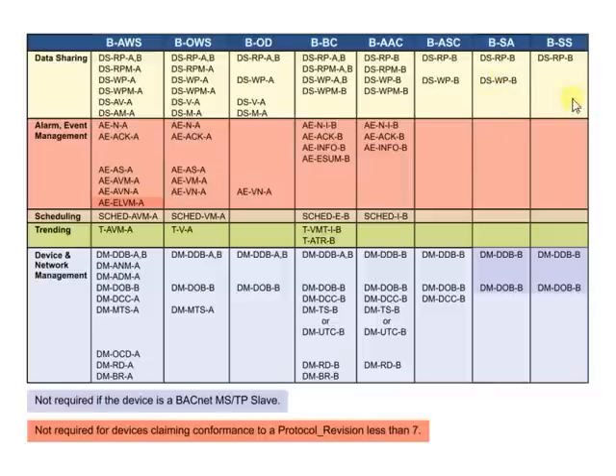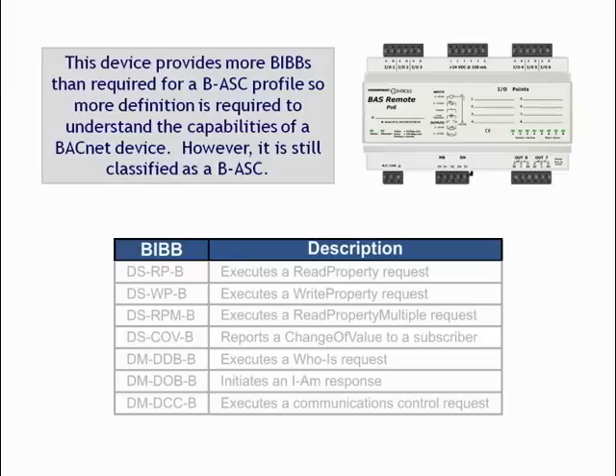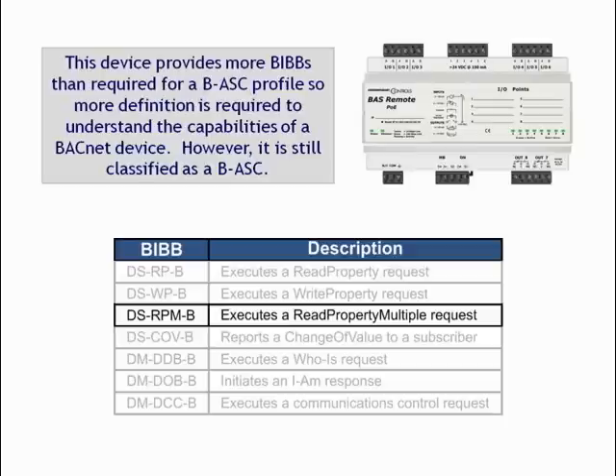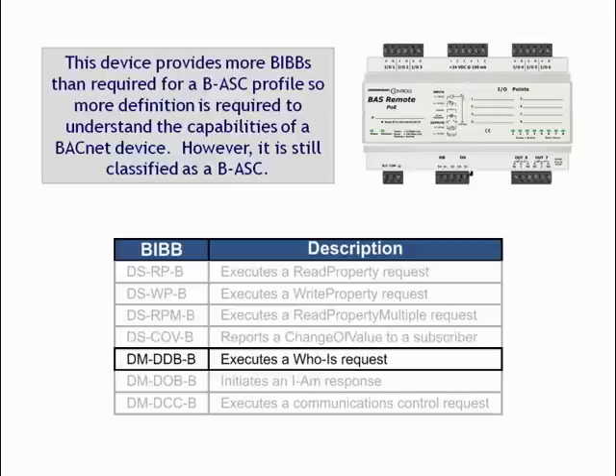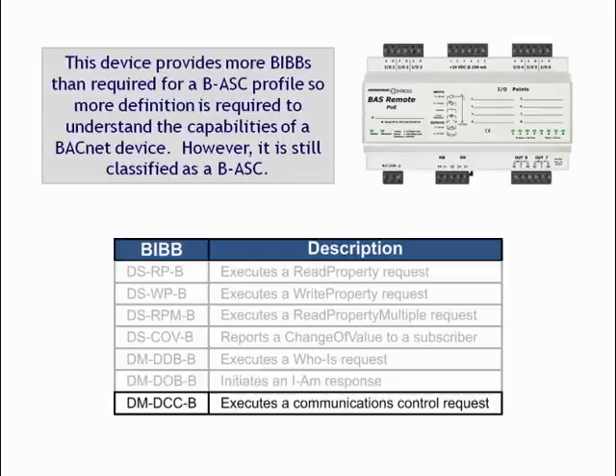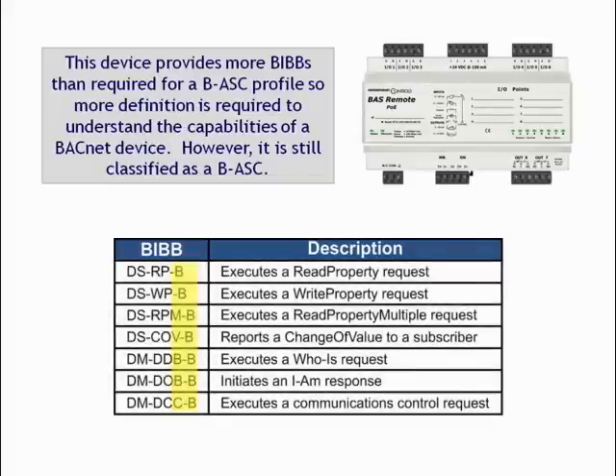Adding BIBs beyond the minimum does not jeopardize the classification. We will do an example of an Application-Specific Controller, tagged B-ASC. This device supports seven BIBs: read property, write property, read property multiple, change of value, executes a who-is request, initiates an I-am response, and executes a communications control request. Notice all these BIBs are B services, which means the device is responding to a request, and therefore is a server and not a client.